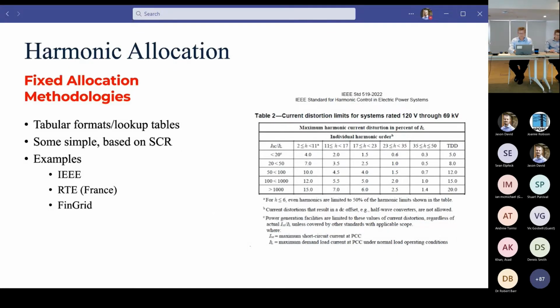And so the table on the right-hand side here is taken directly out of IEEE 519. What you can see is that based on the short circuit ratio of your installation, you will receive a harmonic current emission limit allocation across each harmonic order based on how strong the network is in ratio to the size of the connection itself. Very simple. That's all the information that you need to actually apply this process.